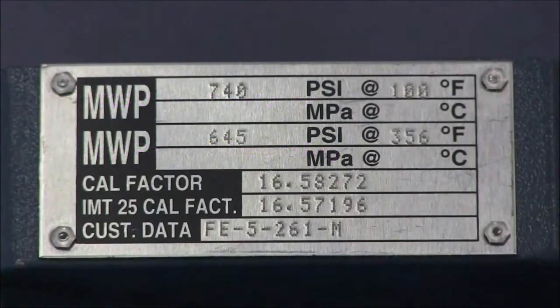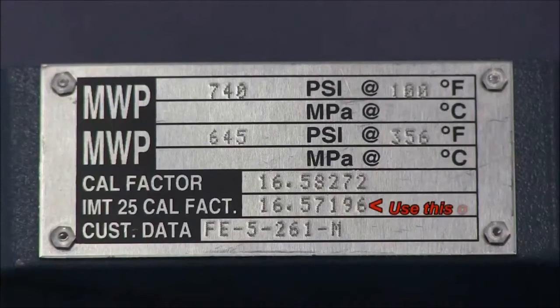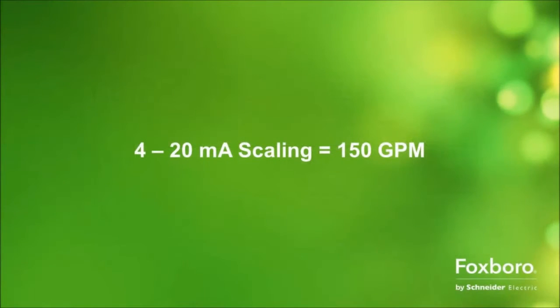Here we show a data plate from an 8000 series flow tube. Since we'll be configuring an IMT25 transmitter, we'll use the IMT25 calibration factor. For this example, we'll use an upper range value scaling of 150 gallons a minute.